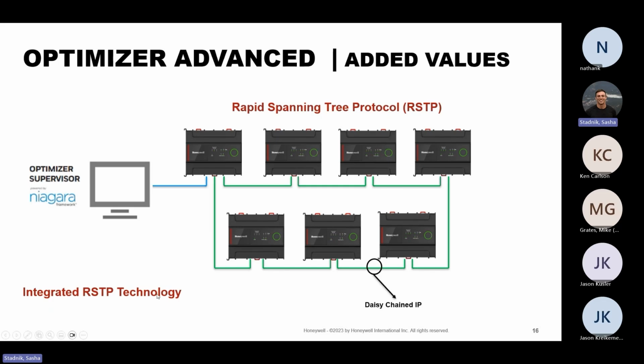So this controller and this controller and this controller and this controller are MSTP controllers, and I have the token here. If I need information from this other controller, that token is going to pass on a daisy chain - that is why it's called a daisy chain. Serial communication protocol, serial chain. And the token passes through, then this controller starts to talk, and the rest are going to listen.